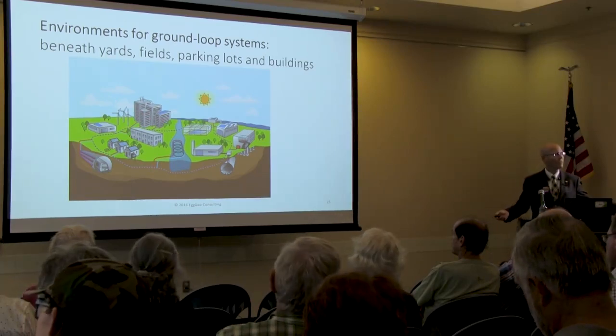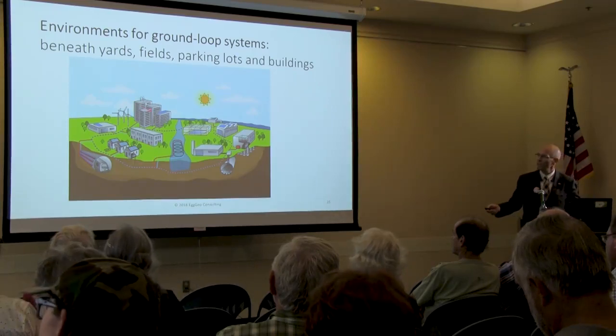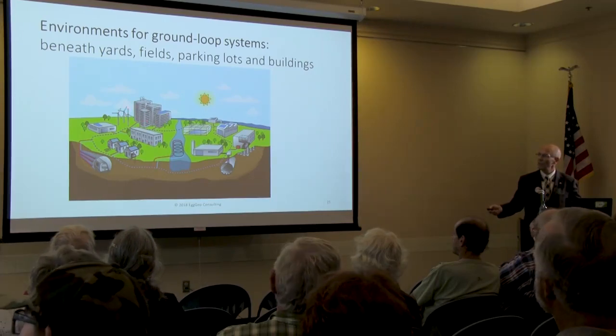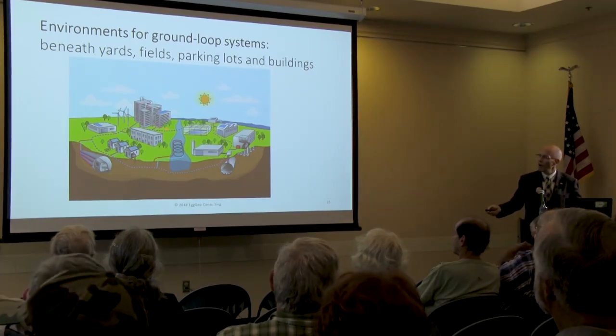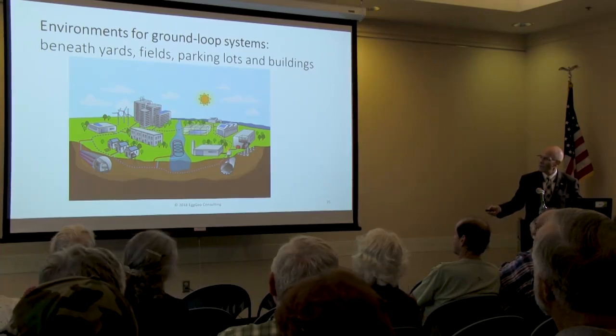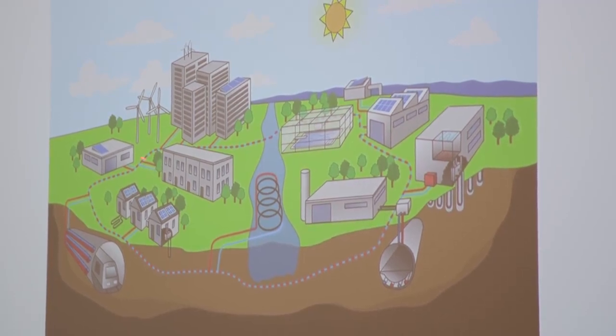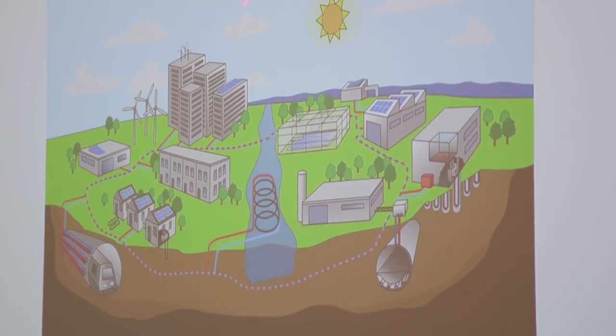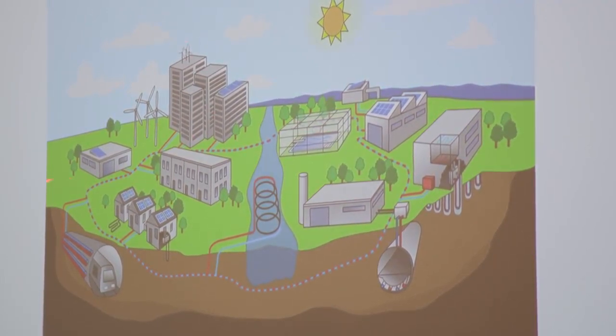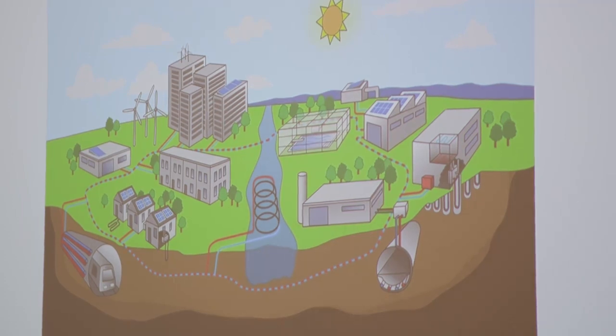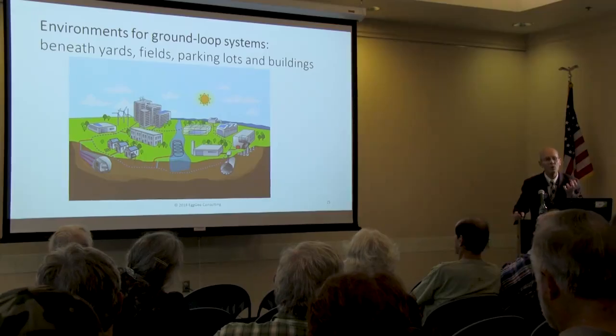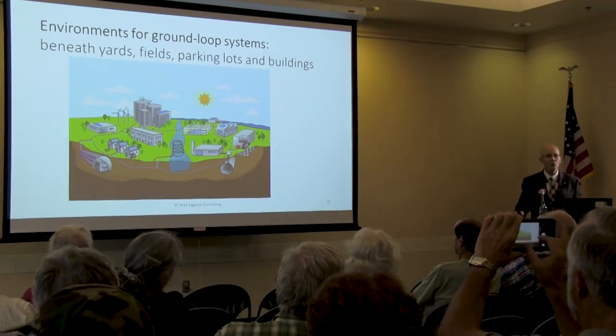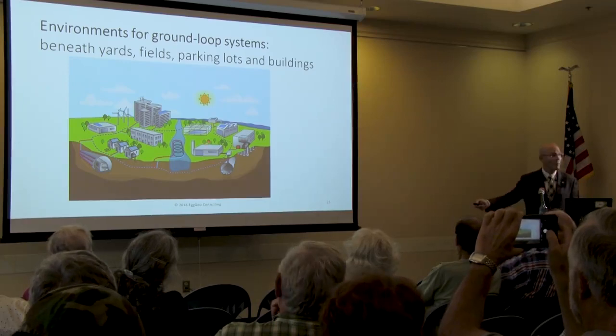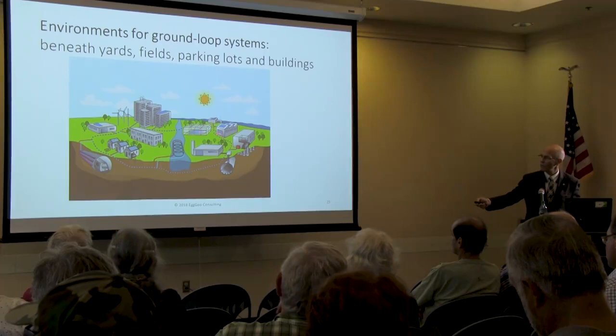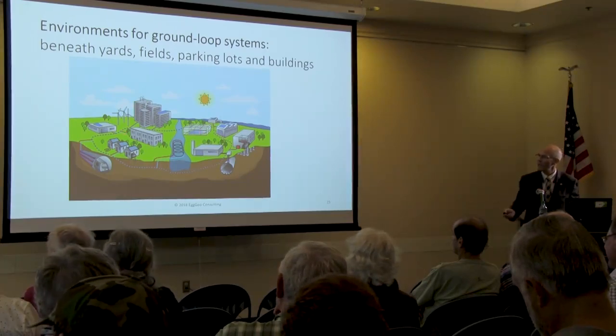These buildings, now it looks like a rosy summer or spring picture here, but imagine this is wintertime and these buildings still have excess heat that they're pumping out and it's snowing outside. This is what a thermal energy grid interconnectivity pipeline looks like, because the energy, instead of going out the cooling towers on the roof, is forced down into this grid, is then extracted from this grid by these apartments that need the heat. So they're taking an incredible millions of BTUs and putting them into this thermal energy grid that can then be used by apartments, by swimming pools, public recreational swimming pools, by anything, by residential homes, anybody that needs this process heat.